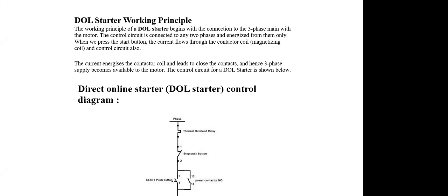But as we know, this is a basic starter, and there is a restriction on using it. Generally, we follow this direct online starting up to 7.5 HP. But this is again requirement based. If we have our own substation or own captive power plant, then we can use direct online starter up to 60 HP, 100 HP also.